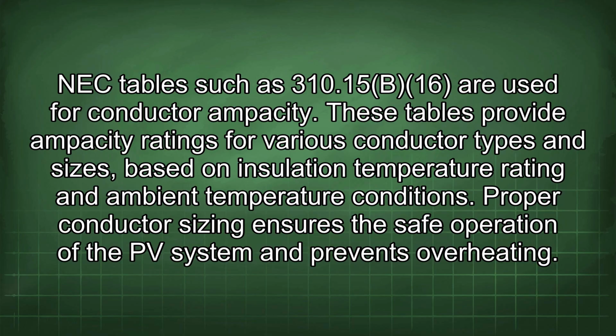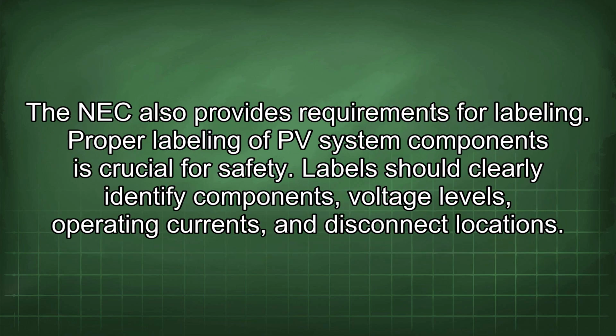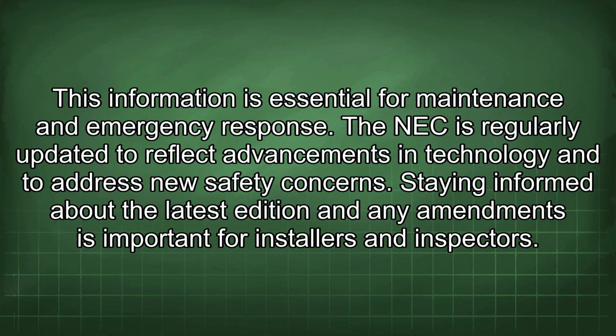NEC tables such as 310.15(B)(16) are used for conductor ampacity. These tables provide ampacity ratings for various conductor types and sizes based on insulation temperature rating and ambient temperature conditions. Proper conductor sizing ensures the safe operation of the PV system and prevents overheating. The NEC also provides requirements for labeling. Proper labeling of PV system components is crucial for safety. Labels should clearly identify components, voltage levels, operating currents, and disconnect locations. This information is essential for maintenance and emergency response.